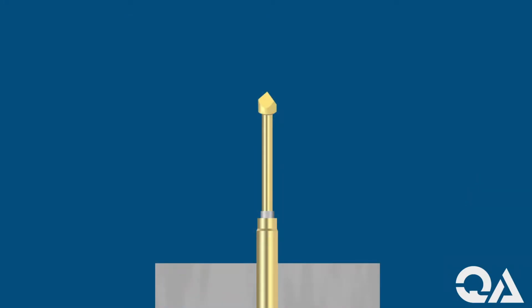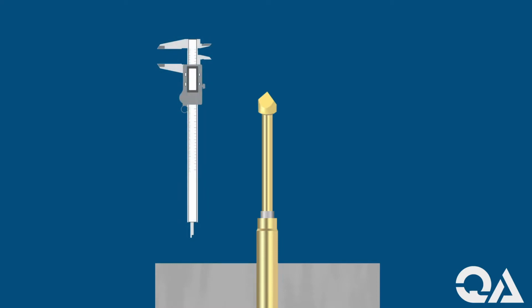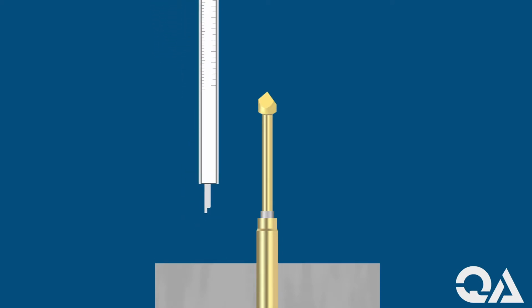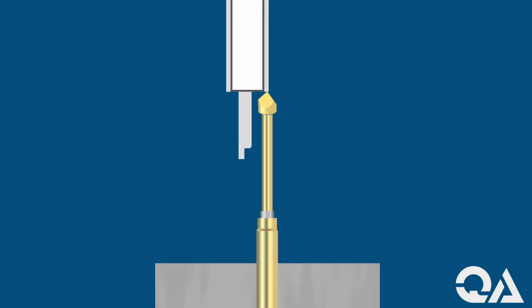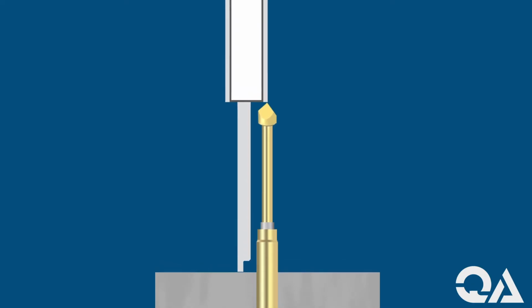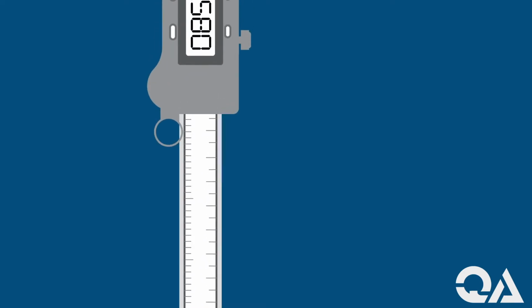To begin, we need to know the height of the existing probes in the fixture. Handheld calipers are perfect for this. Measure from the top of the probe plate surface to the tips of the standard unactuated probes at each location where indicator probes will be used. Capture these measurements and save for later. This will be used as dimension A.